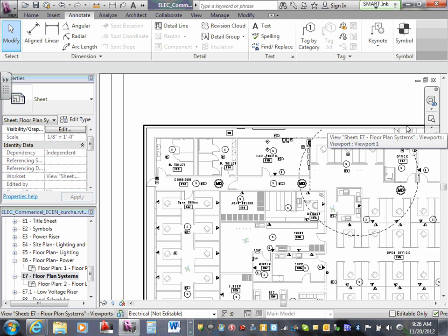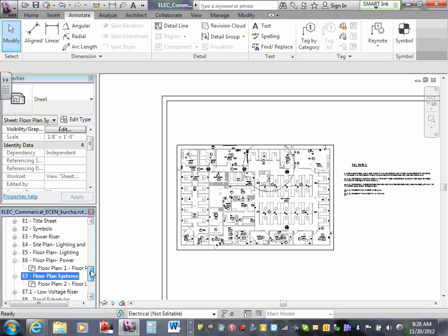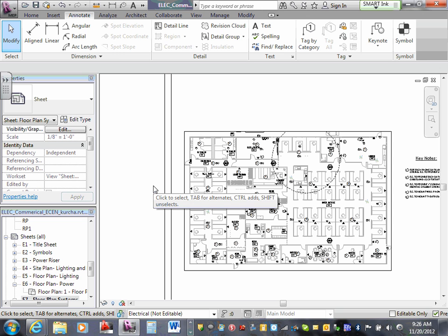How long are the battery backups supposed to last? I believe it's 90 minutes, Jeff. Yeah, that sounds about right. I'll give it an hour and a half. Yeah, 90 minutes. And at 90 minutes, the voltage should not drop below 82% of the rating. But I think if the initiating devices are running, it's lower than that. That's 90 minutes of backup, so if you lose power right now, we have an hour and a half for the battery to maintain the system. But if you have an alarm, you can't maintain all the strobes for 90 minutes. Well, it's such a small building, too. Everybody's going to be out. Yeah, 15 minutes at the most, I would say.